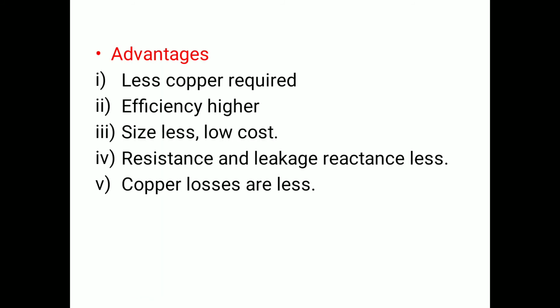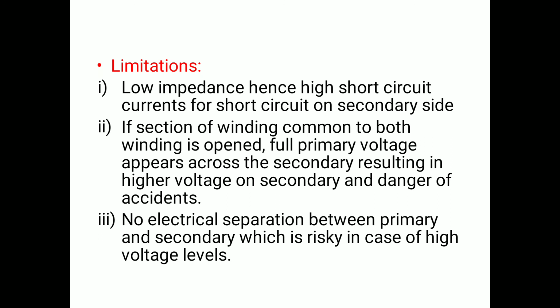Now advantages: because of only one winding, less copper is required, efficiency is higher, size is less, low cost, resistance and leakage reactance is less, because the resistance depends on length and cross sectional area of a wire. Here wire material is less in quantity, so resistance is also less, copper losses are less.